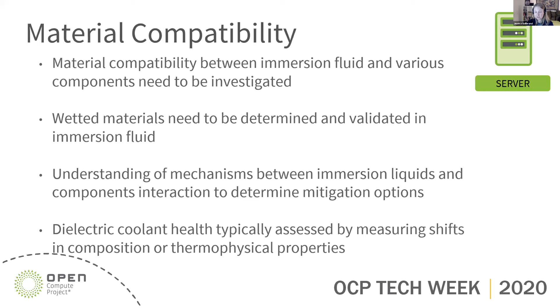In the immersion world, we divide the liquids into hydrocarbon fluids and fluorochemicals. For hydrocarbons like oils, you need to do a general compatibility test. You can put samples, materials or components into a liquid and potentially stress it, right? Thermally stress it, or use other ways of stressing the compatibility testing that you're doing. When you're dealing with fluorochemicals, specifically for single phase, these fluids are very inert, but there might be materials that leach out into the liquid and get deposited somewhere else. They might interact with some other materials that you have somewhere else on your system.